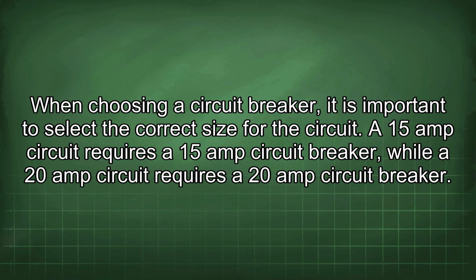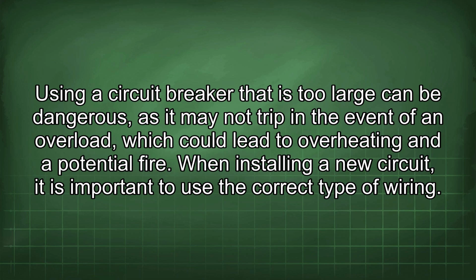When choosing a circuit breaker, it is important to select the correct size for the circuit. A 15-amp circuit requires a 15-amp circuit breaker, while a 20-amp circuit requires a 20-amp circuit breaker. Using a circuit breaker that is too large can be dangerous, as it may not trip in the event of an overload, which could lead to overheating and a potential fire.